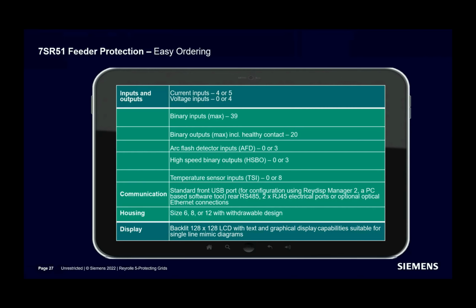And if you choose to add the arc sensor, arc flash detector module, then you will have an extra 3 high-speed outputs inside the arc module, which makes 6 in total. Alongside the binary inputs and outputs, additional AFD and TSI modules are available to add to the hardware configuration. So depending on the binary input, output, AFD, and TSI module selections, the case forms will be size 6, size 8, or size 12.